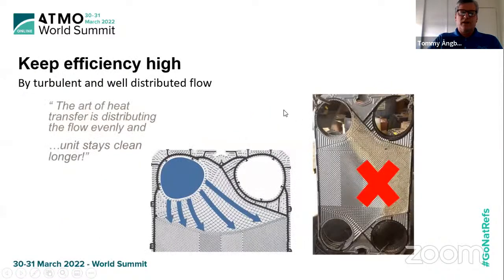Yeah, and also throughout the operation, the efficiency can be kept by assuring the same type of distribution we talked about of the plate type. For efficiency reasons, we can also use that on the water side because this will self-clean the surface, and you will not have dead spots where you could have fouling, and then the efficiency would fall. So it's not just new brand. You have to think over time as well to keep the efficiency high.